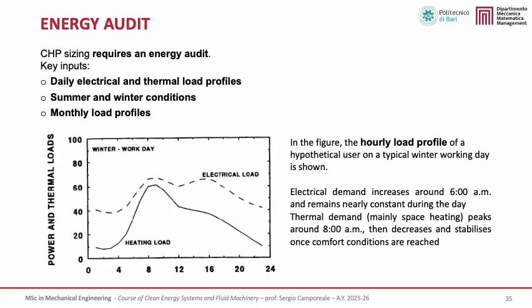The energy audit is absolutely necessary in CHP sizing and should be focused on daily load profiles and annual profiles. The energy audit is a fundamental step in CHP design, as it provides detailed information on how electrical and thermal demands vary during the day under different operating conditions. The figure shows how the hourly load profile of a hypothetical user varies on a typical winter working day.